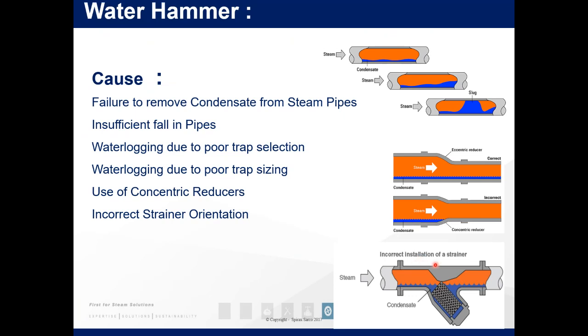Incorrect installation of strainers. As we were saying earlier, a condensate trap should be vertical. So this should be facing downwards, as it shows in the picture. This allows the particles to come along, catch in the strainer, and then the condensate passes along without taking them with it. With a steam trap, we don't want the buildup of condensate in here because that could then produce the slug. So we would have this strainer facing towards us, so there can't be a collection of water.